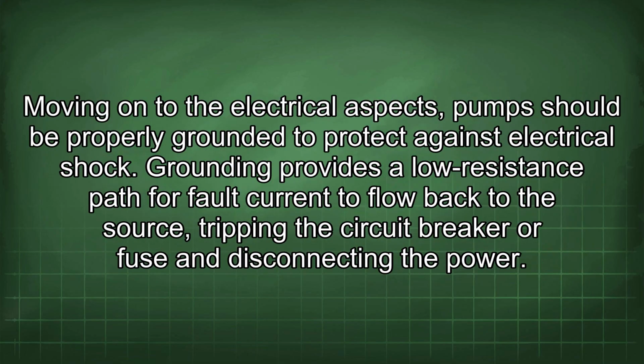Moving on to the electrical aspects, pumps should be properly grounded to protect against electrical shock. Grounding provides a low resistance path for fault current to flow back to the source, tripping the circuit breaker or fuse and disconnecting the power.